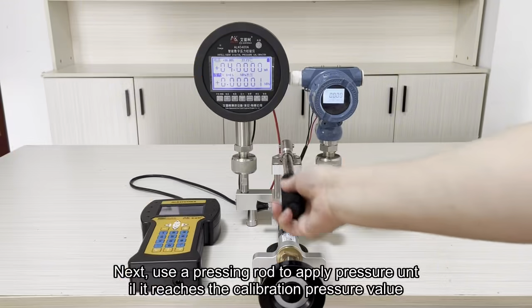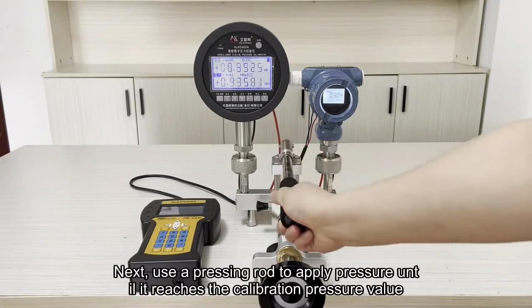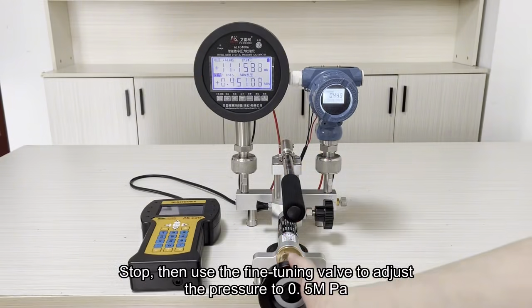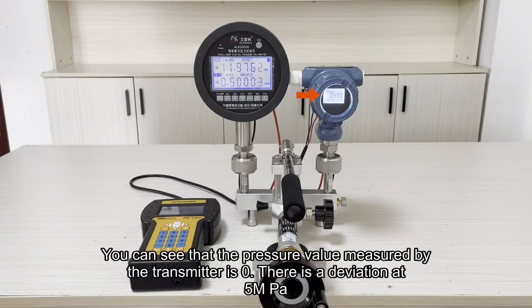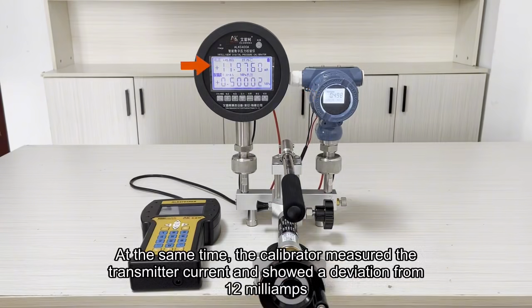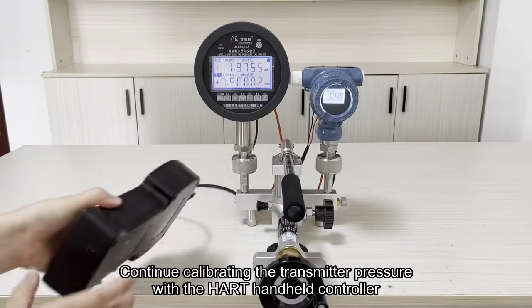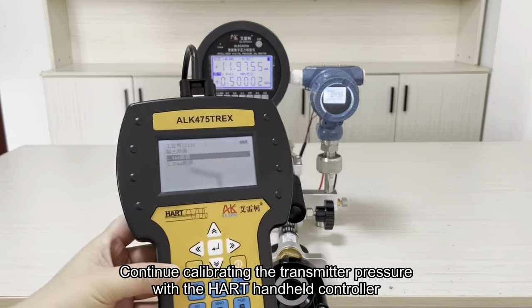Calibration successful. Next, use a pressing rod to apply pressure until it reaches the calibration pressure value. Stop, then use the fine-tuning valve to adjust the pressure to 0.5 MPa. You can see that the pressure value measured by the transmitter is not 0.5 MPa. There is a deviation at 0.5 MPa. At the same time, the calibrator measured the transmitter current and showed a deviation from 12 mA. Continue calibrating the transmitter pressure with the HART handheld controller.